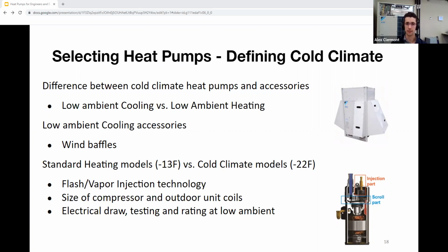Now, going back to heating, there's actually two different kinds of models, or two different kinds of units. There's cold climate units with heating data down to -22. There's also standard heating machines with heating data down to -13. And the main difference between cold climate machines is the larger vapor injection compressors, and also larger coil surface area, which does result in more modules. Now, cold climate models, the -22 models, have also tested and designed their MCAs and MOPs of those condensing units at lower ambient temperatures. So they're tested at lower temperatures compared to the standard heating models.